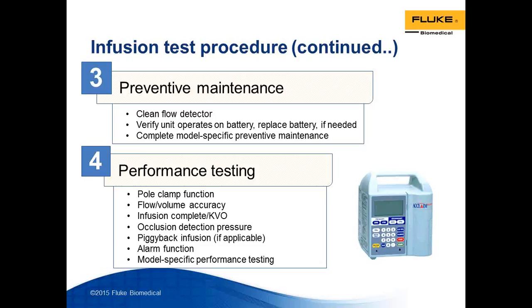Then comes preventative maintenance, which is looking at the flow detector, verifying that the unit is operating okay in terms of the LEDs and batteries, and performing maintenance such as replacement if necessary. There is also some model-specific preventative maintenance based on the manufacturer and the model of the infusion pump. And finally, the performance testing, which is making sure that the infusion pump is actually providing the medication as specified.